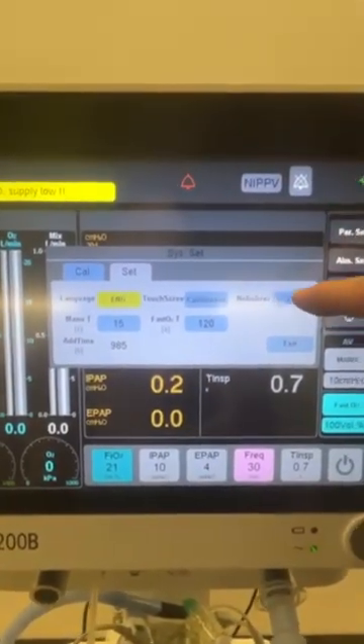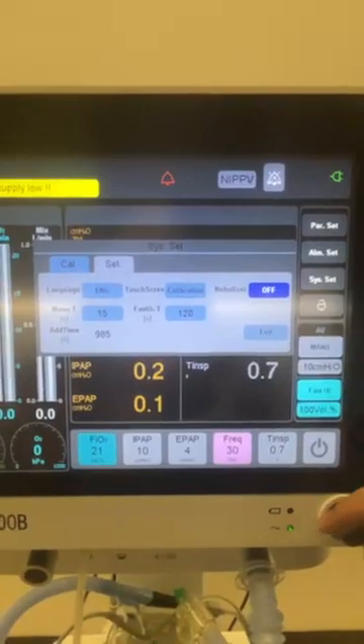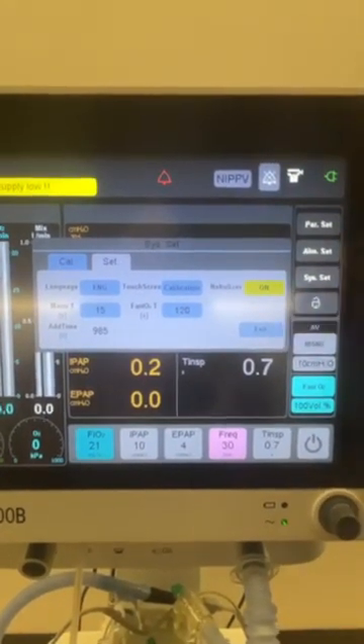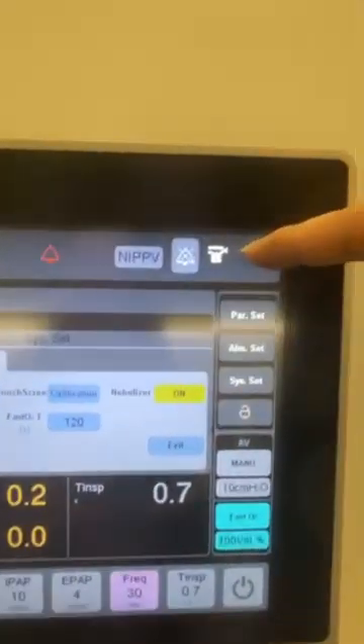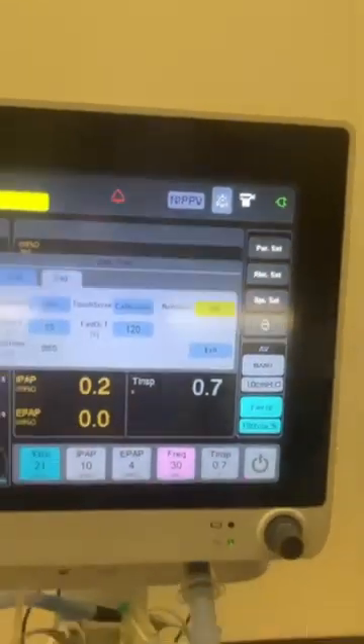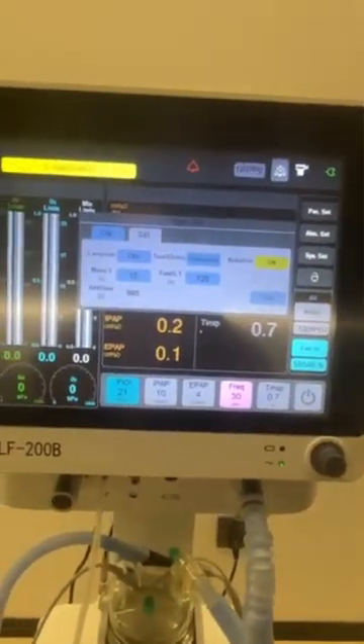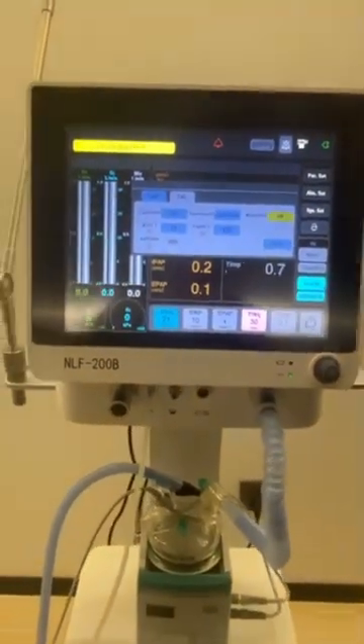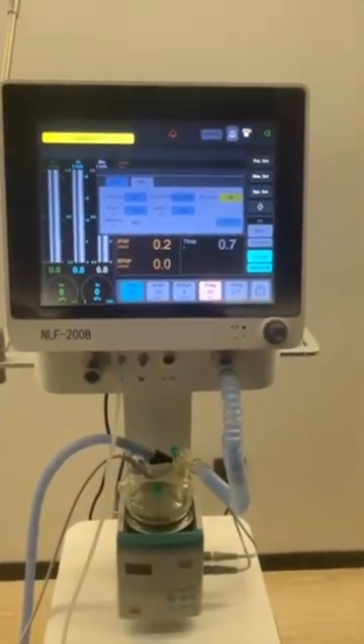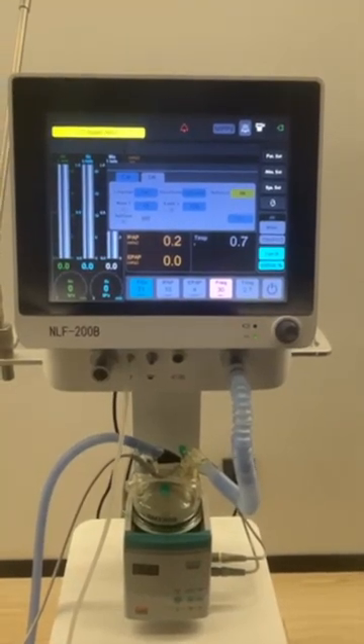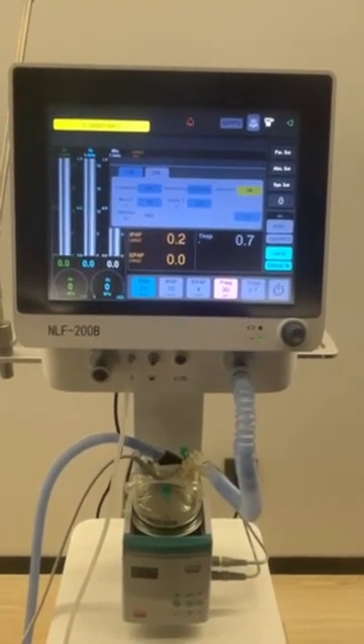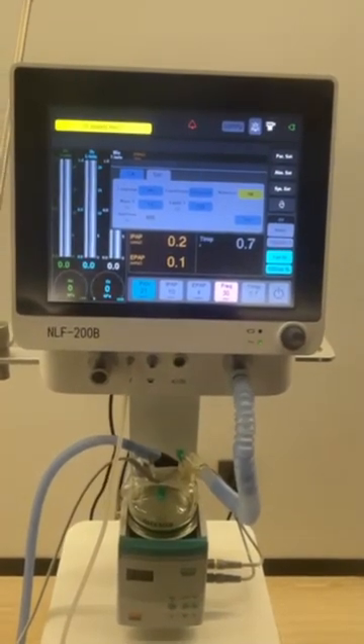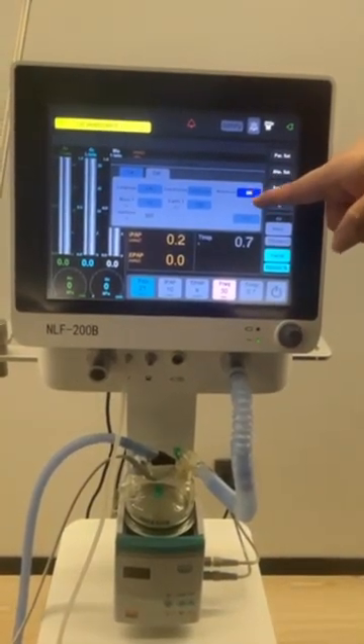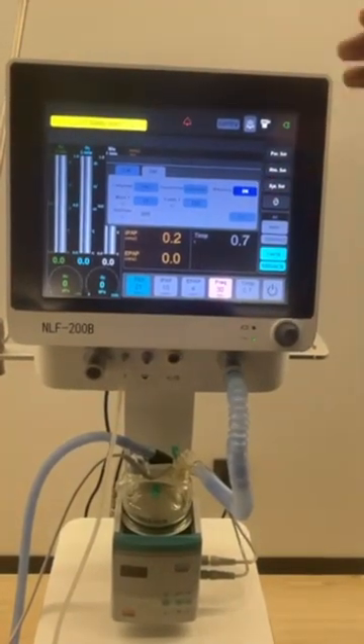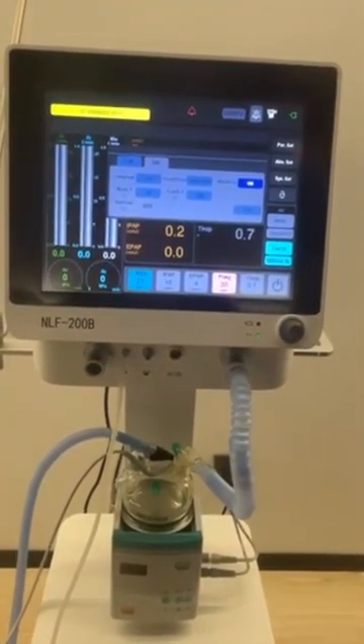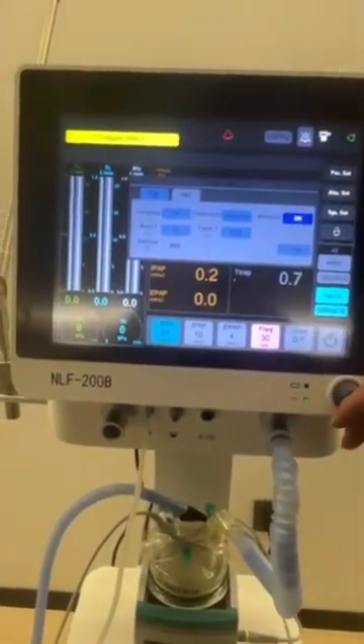And the third button is the nebulizer. Once we turn it on, we can use the nebulizer function, and you will see a symbol here. It means we are now using the nebulizing. Because this machine is especially used for neonates and children under 30 kilograms, mostly this kind of patient will need to do nebulizing with medicine to be breathed in to cure some illness. So this function is very important. Once you press it, the nebulizer function runs automatically, and if you want to finish, you just turn it off again.